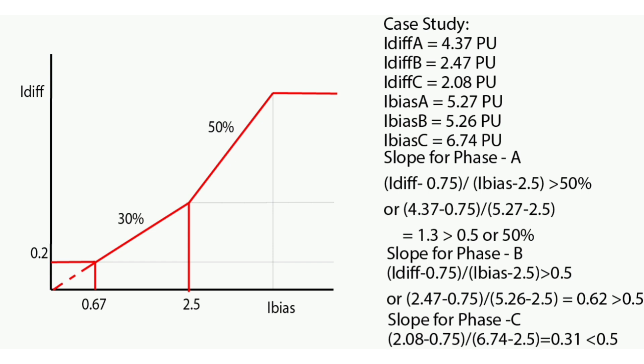The slope can be calculated to check whether it is greater than 50% for all phases. For phase A, the slope is calculated by the formula: (I_differential minus 0.75) divided by (I_bias minus 2.5), which must be greater than 0.5. Here, differential current for phase A is 4.37 per unit and bias current is 5.27 per unit. So slope equals (4.37 minus 0.75) divided by (5.27 minus 2.5), which equals 1.3 — greater than 0.5. The differential current for phase A remains beyond the 50% region, in the tripping zone.